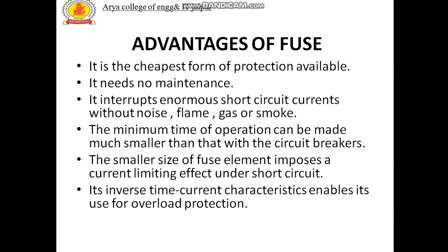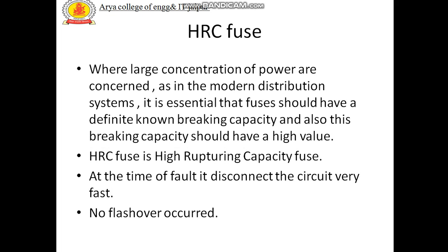The minimum time of operation can be made much smaller than that with circuit breakers. The smaller size of fuse elements imposes a current limiting effect under short circuit, and the last one is that its inverse time current characteristics enable its use for overload protection.